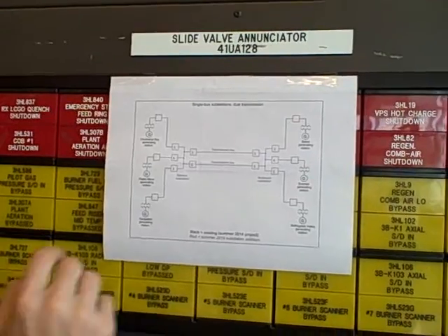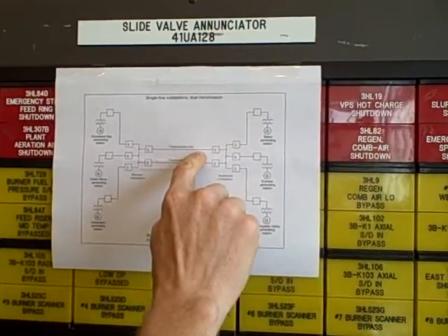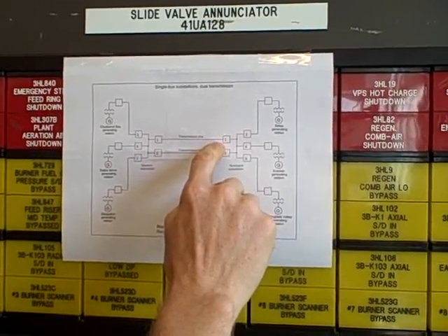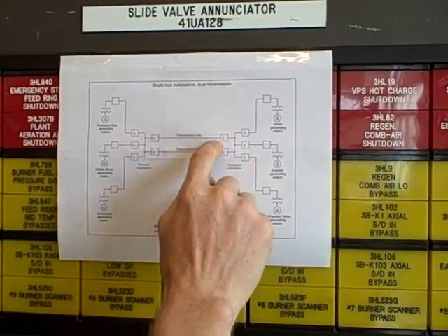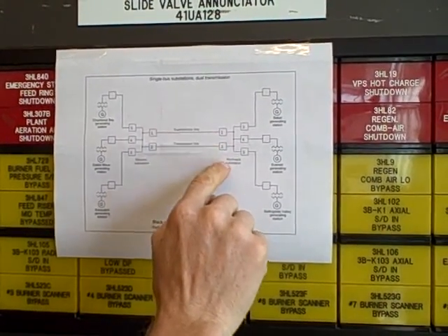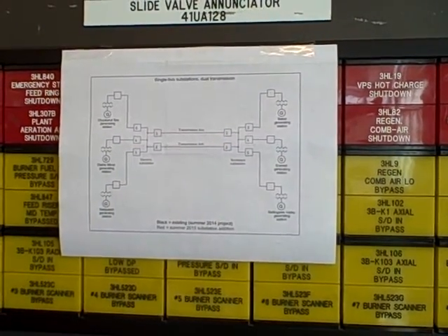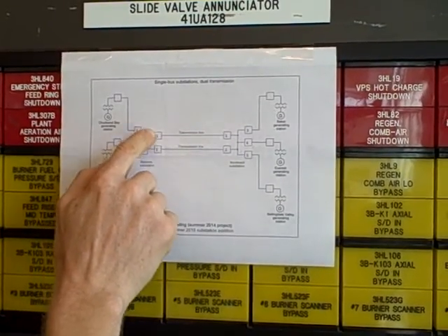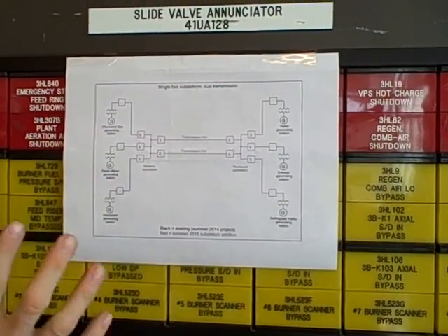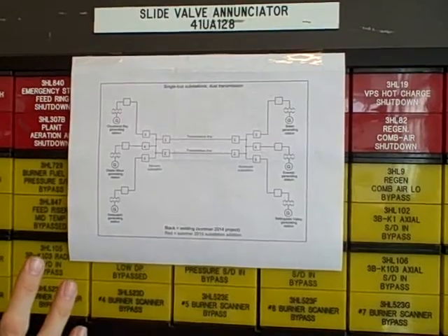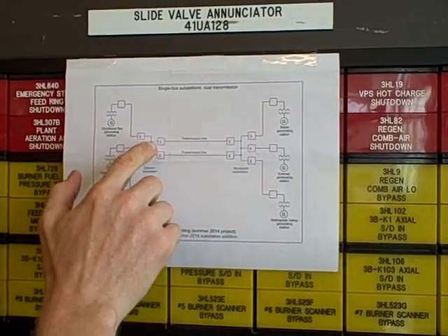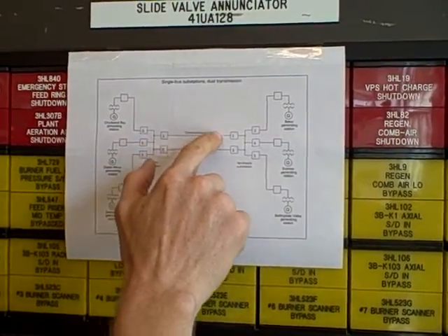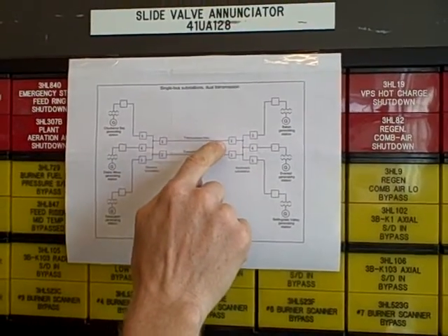We have placed a fault on this transmission line. We have shorted one phase to another at the very end of that line, really at the entrance to the other substation, Nooksack. When we close breaker number four, that's going to energize the bus of Stevens, and that by itself will not pose any problem. But once we close breaker one after closing four, that's going to energize that transmission line where the fault is.